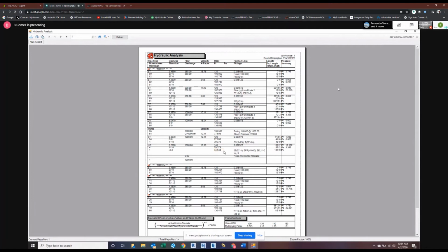Now, you did mention something about 65 psi. So part of this might be that when this building was constructed, and there still are some existing considerations in NFPA as well as the ICC codes with regard to standpipe systems, specific classification of standpipe systems where 100 psi at the roof is not required. Instead, 65 psi is required. Old versions, I think 65 was the standard. It didn't used to be 100, but that was way back when, long before I even knew.